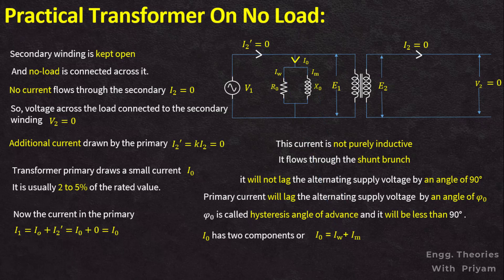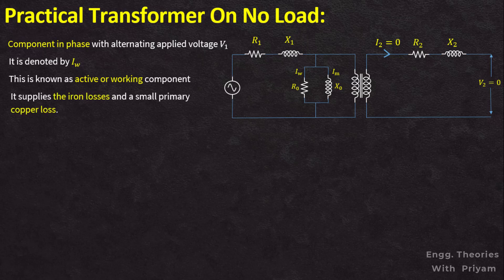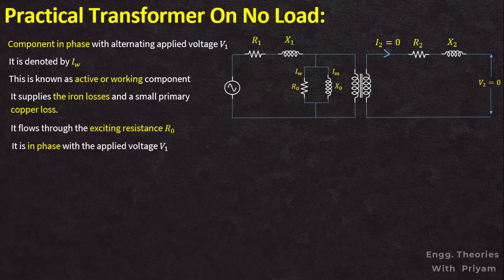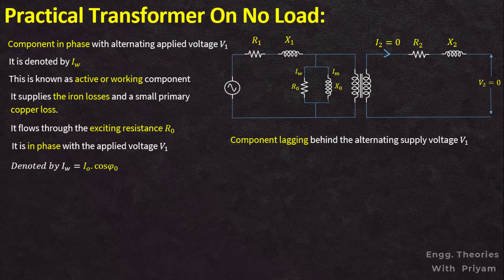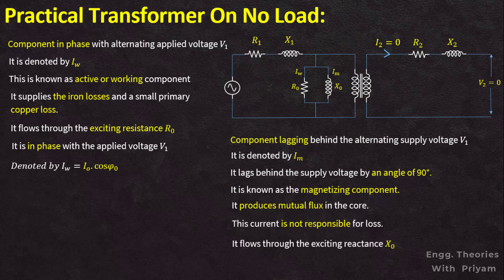The current I₀ has two components: I₀ = Iw + Im. The component which is in phase with the alternating voltage V1 is denoted by Iw and is called the active or working component. It supplies the iron losses, which includes hysteresis and eddy current losses, and a small primary copper loss. It flows through the exciting resistance R₀ and is in phase with the supply voltage V1, denoted as Iw = I₀ cos φ₀. The component lagging behind V1 by 90 degrees is Im, known as the magnetizing component. It produces mutual flux in the core, is wattless, and flows through the exciting reactance X₀.